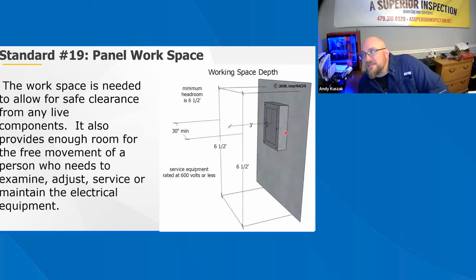Number 19, panel workspace. The workspace is needed to allow for safe clearance from any live components. It also provides enough room for free movement of a person who needs to examine, adjust, service, or maintain the electrical equipment. The space shall be at least 36 inches deep. The workspace should be at least 30 inches in width in front of the electrical equipment and not less than the width of the electrical equipment. If the panel board is wider than 30 inches, the workspace must extend its full width. The workspace should be clear of obstructions. The workspace's height from the floor or platform should be at least 6.5 feet.